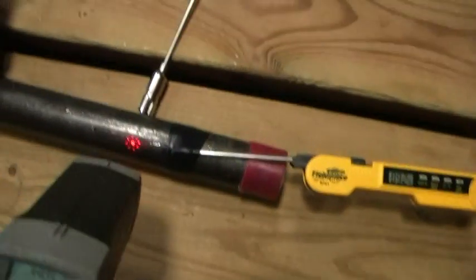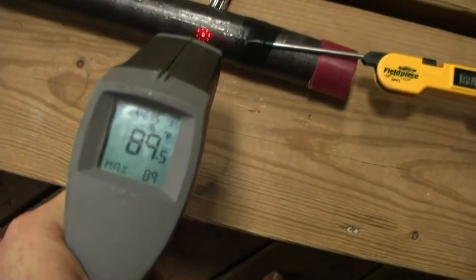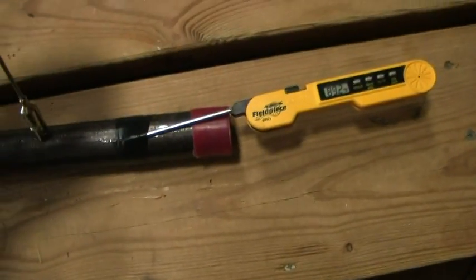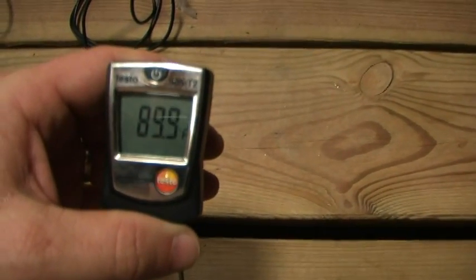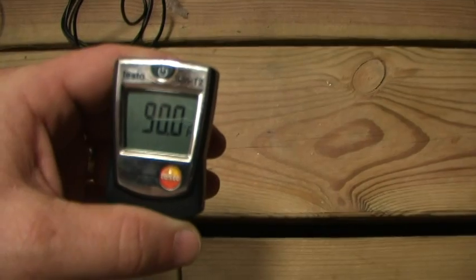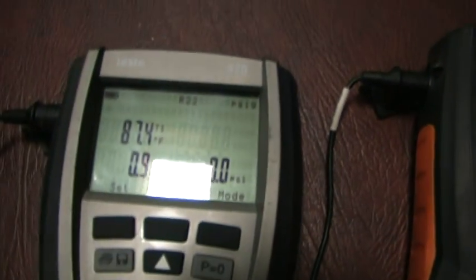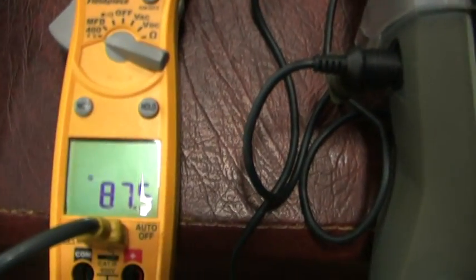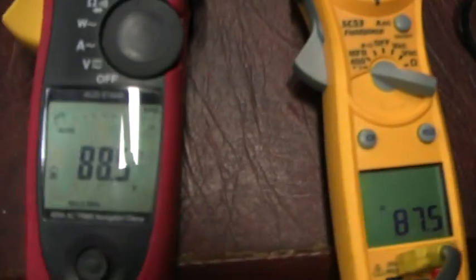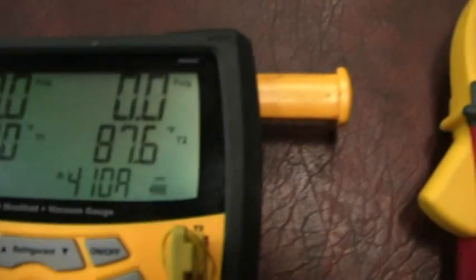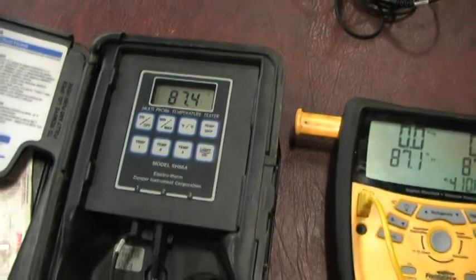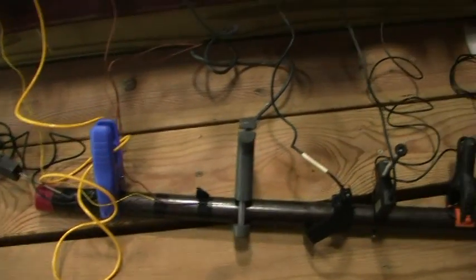Right now this is saying 89. I am on the pipe, it's saying 89. My instant read is saying 89, 90, so yeah right around 90. My 550s are seeing 87, my 570s are 87, my 523s are 87, my Fieldpiece with the Fluke clamp is 87, my amp probe is 88, Fieldpiece both types 87, and my Cooper 87. So everything is either showing to be 87 or 88 degrees.